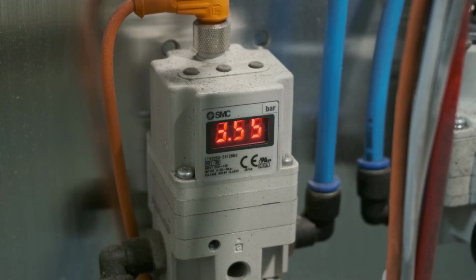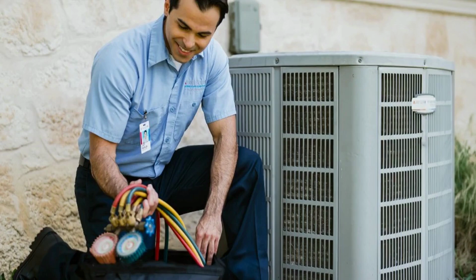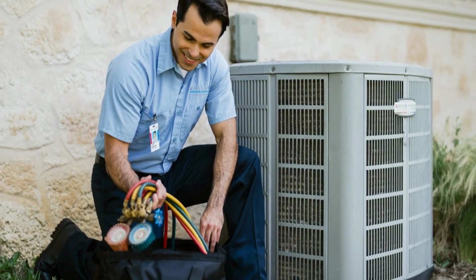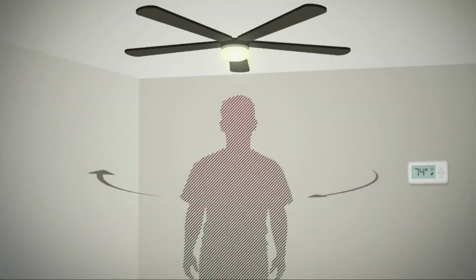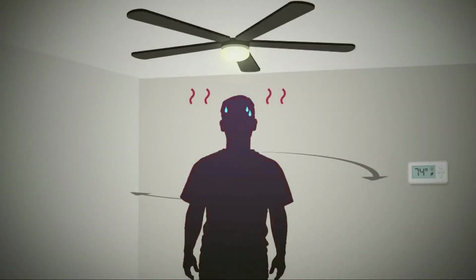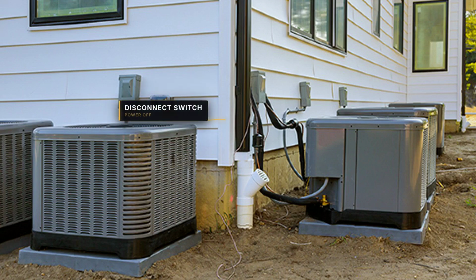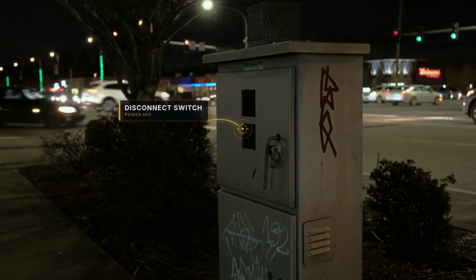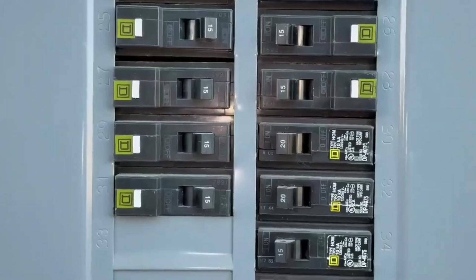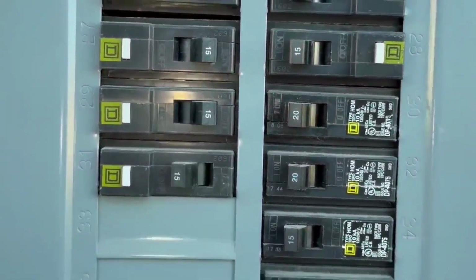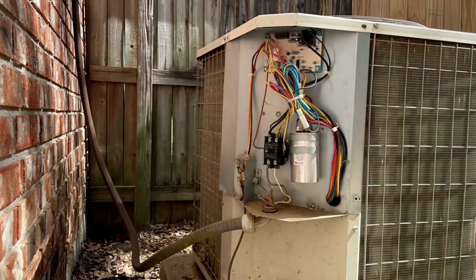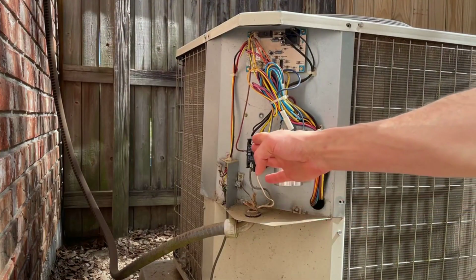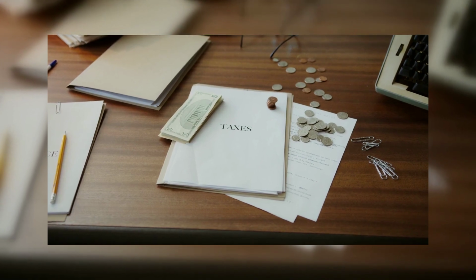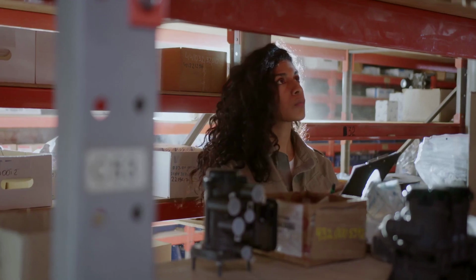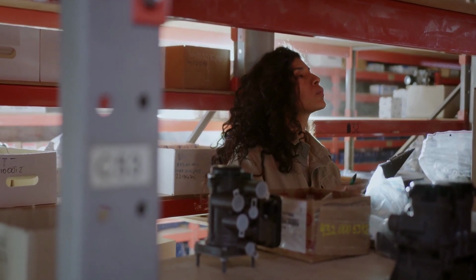Up to this point, the process had been about preparation and knowledge. That was about to flip into hands-on execution. Cut the power first and cut it completely. Turn the AC off at the thermostat. Then flip the disconnect switch located at the outdoor condenser unit, typically a small box mounted on the wall nearby. Then go to your breaker panel and switch off the breaker labeled for the AC or condenser. 3 separate power cuts. All 3 matter. A capacitor replacement is safe when power is fully isolated. Skipping any of these steps introduces unnecessary risk.